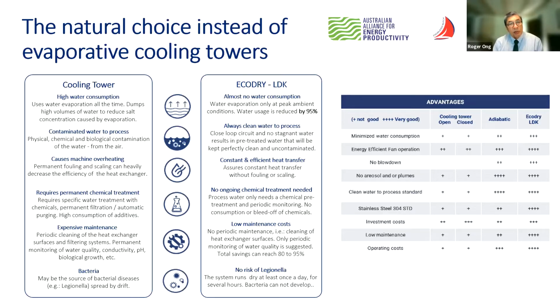Adiabatic coolers to the industry, either as a new site or as a retrofit to replace cooling towers. Most of the common issues we've seen when we deliver a cooling tower retrofit is there's a lot of blockages and scaling problems associated with the process, resulting in loss of flow and poor heat transfer. Consequently, a lot of clients tend to run the cooling tower at a much lower temperature, using more water and more chemical consumption, not to mention high maintenance costs.